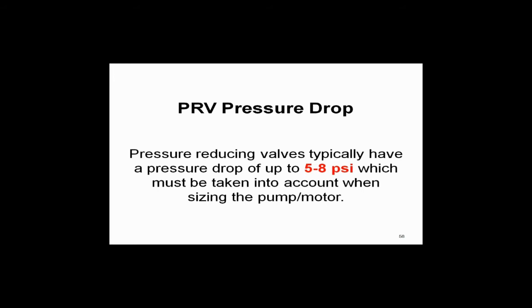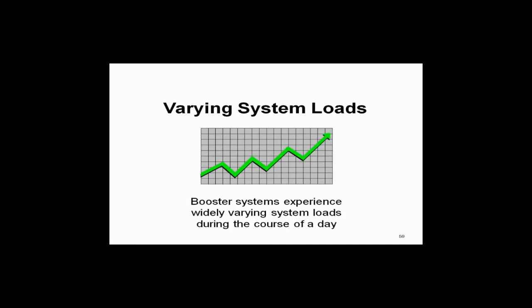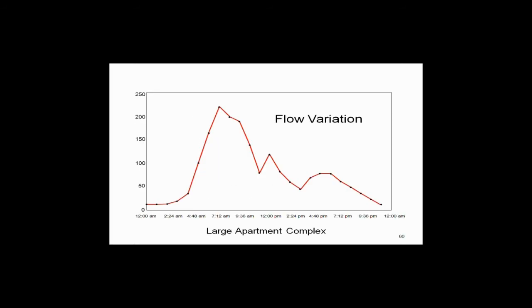Do our loads change? Sure. There's a typical load profile of a complex. In the morning at 12 a.m., the GPM is very low. It peaks at about 225 GPM around 7 o'clock — everybody's taking showers, the kitchen's on, dishwasher's running. At night it drops back down to about 20 GPM. So why would you run a pump at constant speed, sized for peak demand, when you certainly can take advantage of the flow changes in a typical load profile?